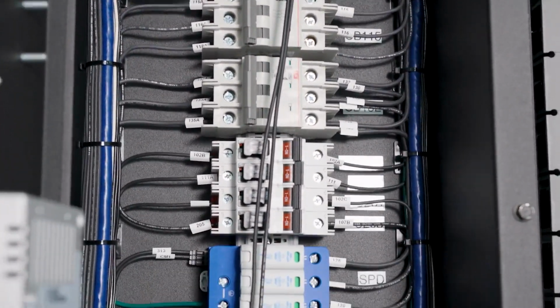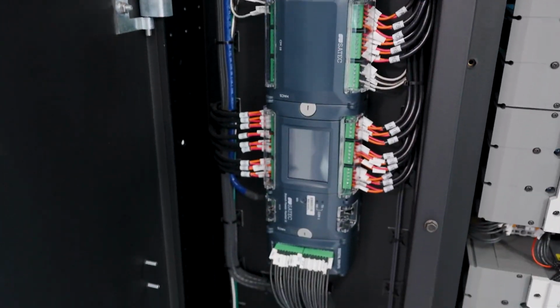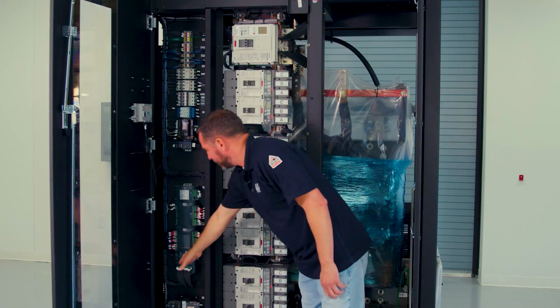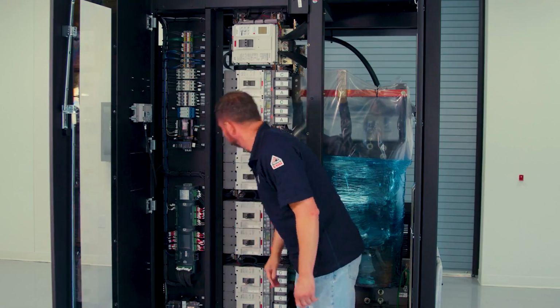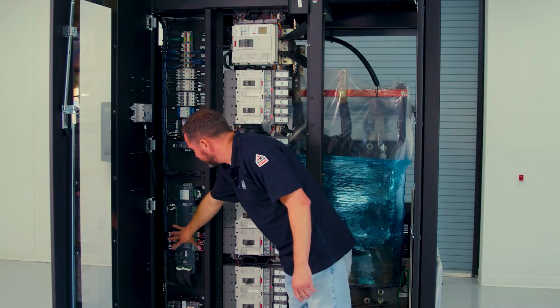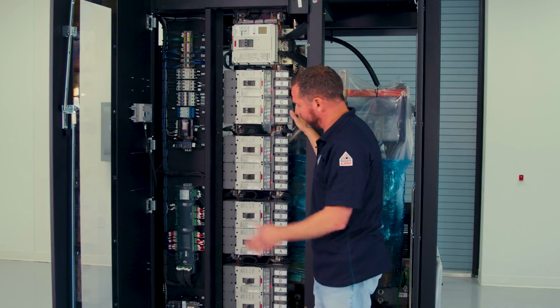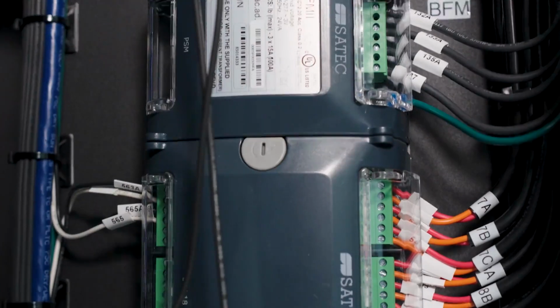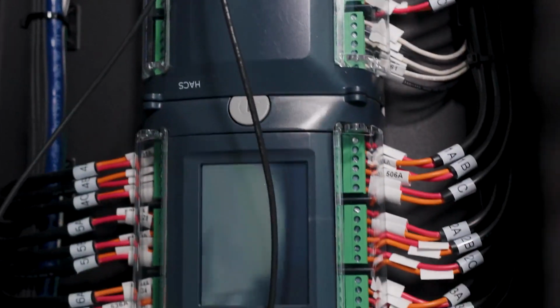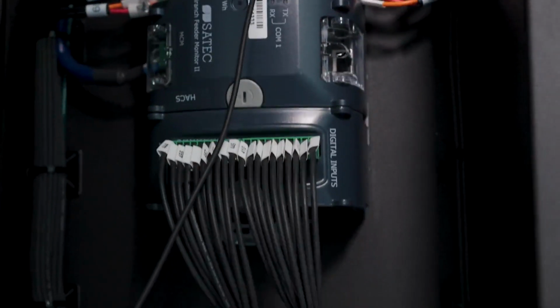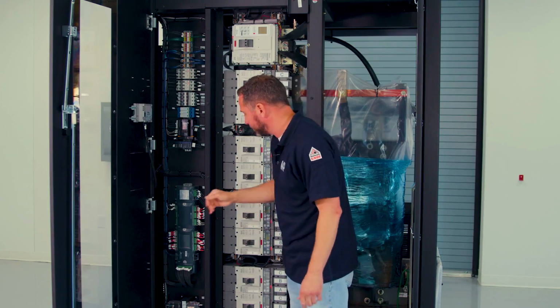Next up, we have our BFM. Well, this whole BFM is actually for all of our feeder breakers. So on the very bottom, we have our open and close for all of our feeder breakers. We also have our CTs for our feeder breakers fed in one of the modules as well. And also we have our HMI on our BFM, so you can see all your information on there, your 415 volt, any other information you want to see, your IP addresses.